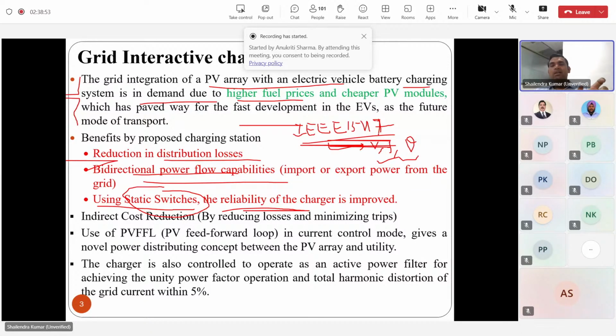They have given some range for these quantities: voltage from 0.8 to 1.1 or 1.2 per unit, frequency within plus minus 0.2 or 0.3 hertz, and the angle difference between the converter output voltage angle and the grid voltage angle must be less than 3 degrees. So these three quantities have been defined.